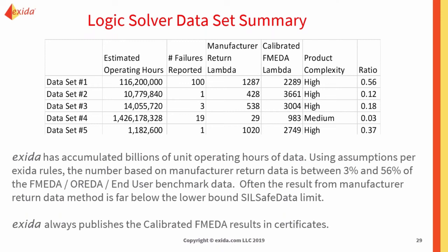So that's not just FMEDAs. It's also looking at end user benchmark studies and OREDA. If you're not familiar with OREDA, it's the offshore reliability data handbook from the North Sea that looks at oil platforms there. And the manufacturer's data studies alone, if you look at them, are often well below generic or even the SIL-safe data limits. So at Exida, we always publish the calibrated FMEDA results in the certificates and the FMEDA report, not just the manufacturer's field return studies, because there are so many assumptions that go into them.